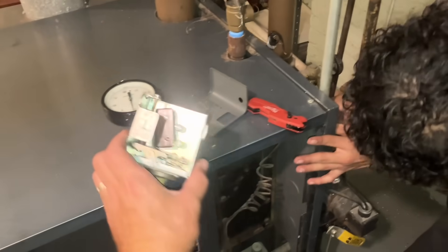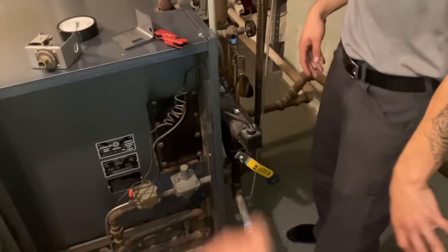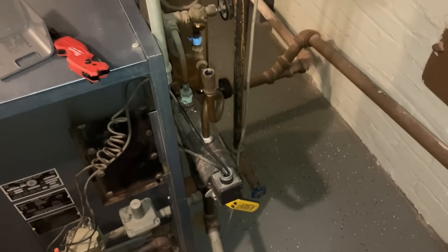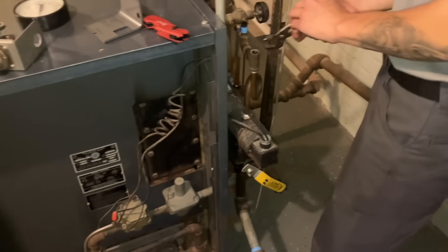Derek removed the two wires going to the pressuretrol. We also removed the pressure gauge. And now he's going to pull out or unthread the pigtail from the top of the number 67 low-water cutoff. We're going to make sure that the pigtail is clean.